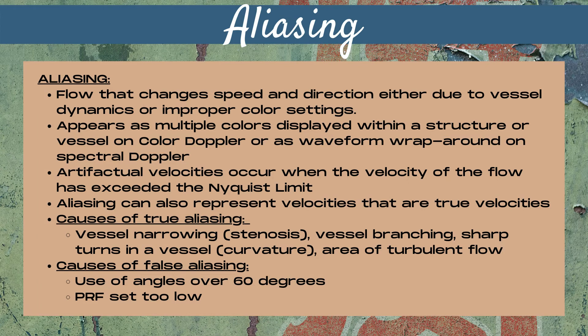Before we can talk about the PRF or scale control on an ultrasound machine, we first have to address aliasing and the Nyquist limit. Aliasing is flow that is changing speed and direction, and it's either going to be due to vessel dynamics or improper settings on the machine. With color doppler, this appears as multiple colors displayed within a structure or a vessel. On spectral doppler, this appears as the signal wraparound on a waveform.